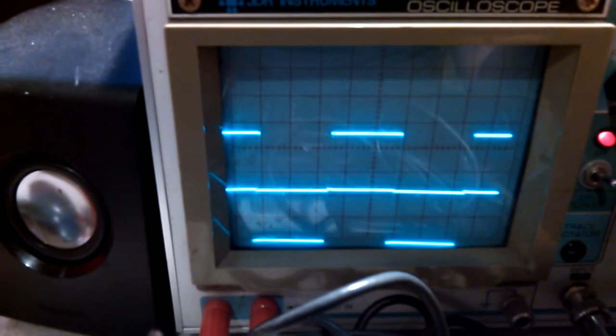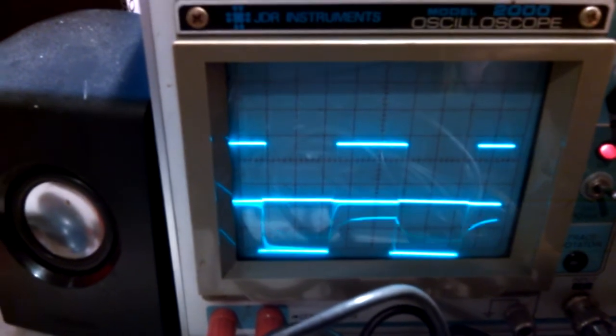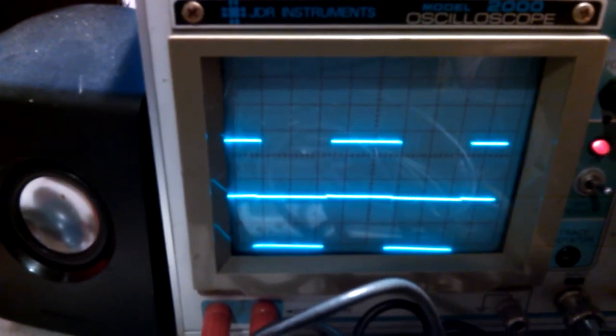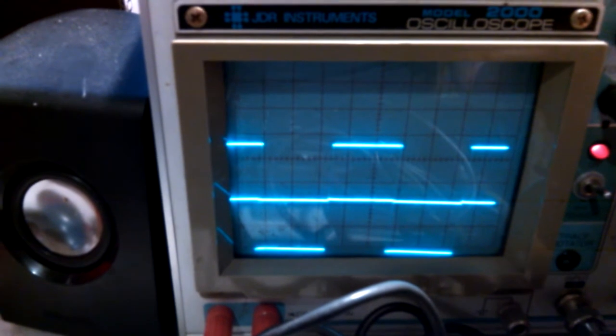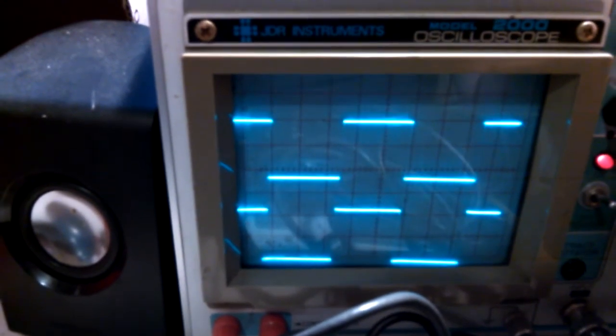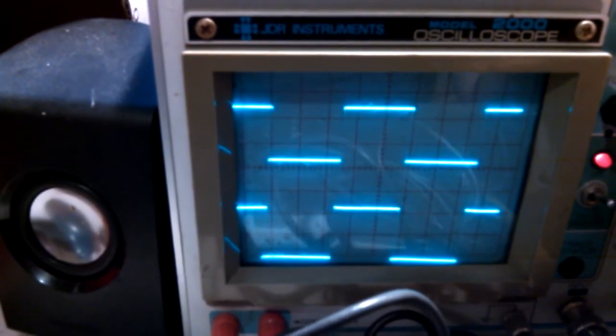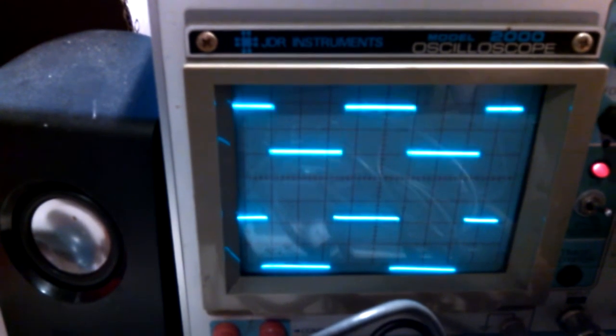You can see if I line it up with the top of the channel 2, it's on the same signals. All that noise is because channel 2 is not very well connected. But you can see here that if I line it up below this point, the attenuation issue doesn't really exist. They're almost identical. But as soon as you get up to about here, you start seeing it attenuate.